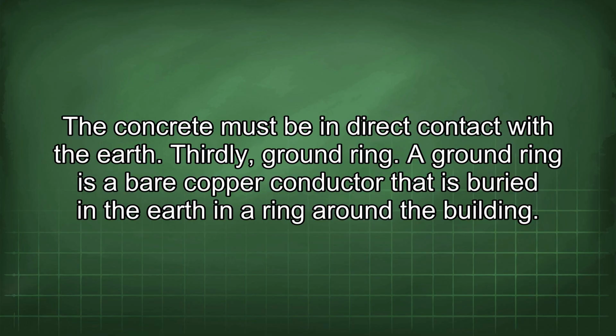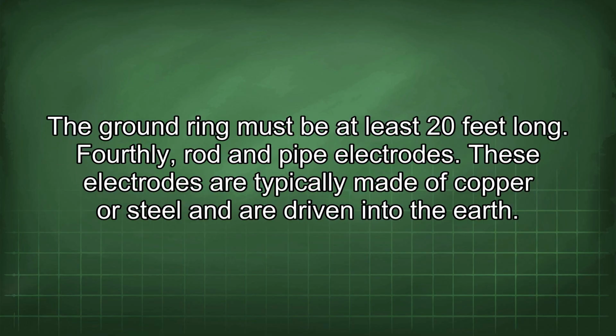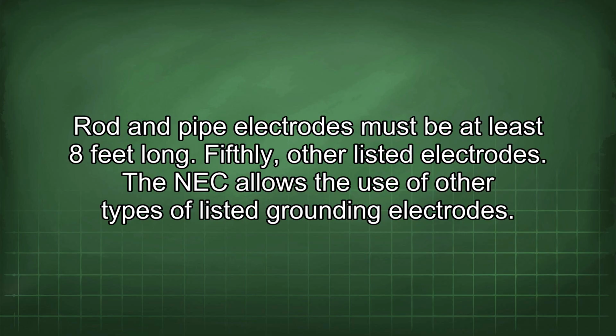Thirdly, ground ring. A ground ring is a bare copper conductor that is buried in the earth in a ring around the building. The ground ring must be at least 20 feet long. Fourthly, rod and pipe electrodes. These electrodes are typically made of copper or steel and are driven into the earth. Rod and pipe electrodes must be at least 8 feet long. Fifthly, other listed electrodes. The NEC allows the use of other types of listed grounding electrodes.